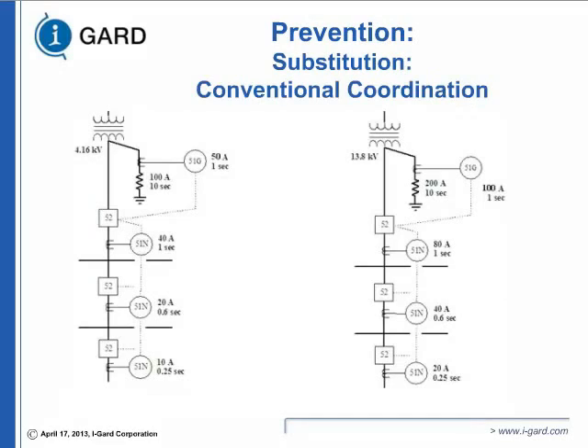So conventional coordination, how do we do that? Normally, as all of you are probably familiar, we increase the magnitude and increase the time delay. So if the fault is downstream of the breaker, the lowest breaker you see, which is set at 10 amp 0.25 seconds, will operate first. If that does not operate, the next is set at 20 amp 0.6 seconds, and that will operate, and so on. At the end you have protection of the resistor. You can notice this is set at 1 second, so it's a very high setting. If you calculate incident energy on these 1.25 seconds, which is 15 cycles, it is going to be pretty high. 15 cycles is a big time.